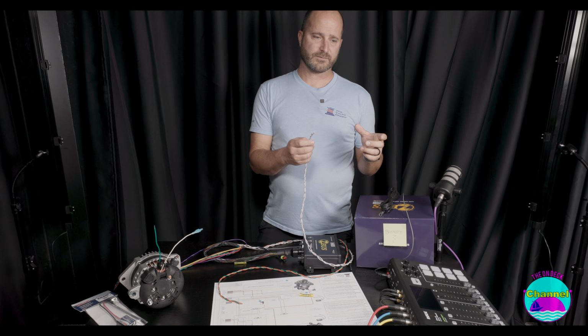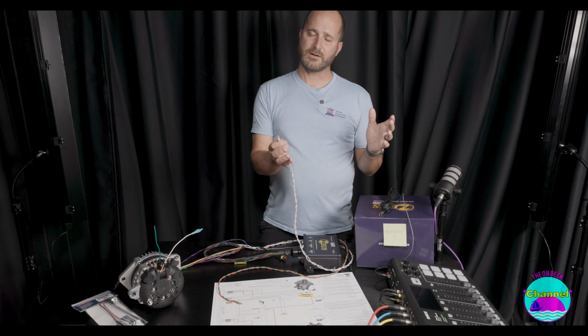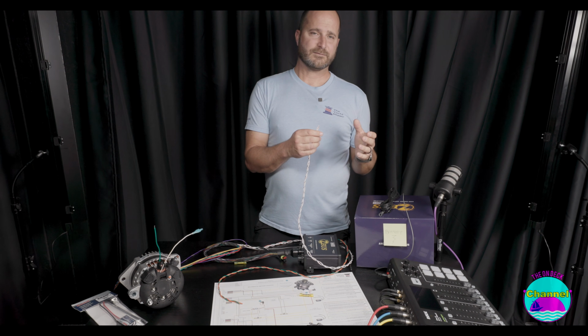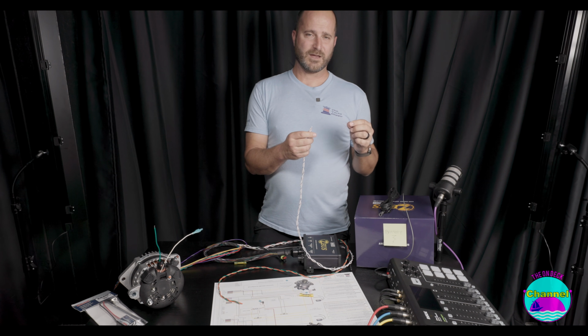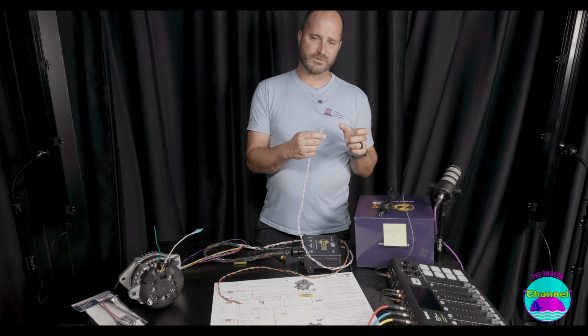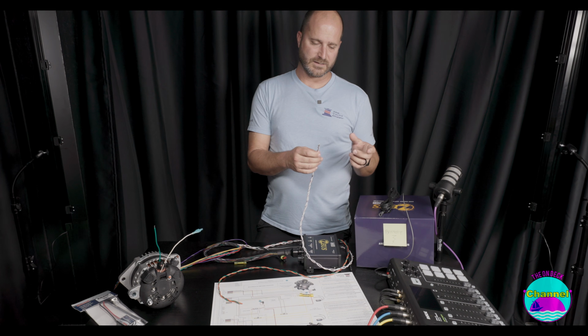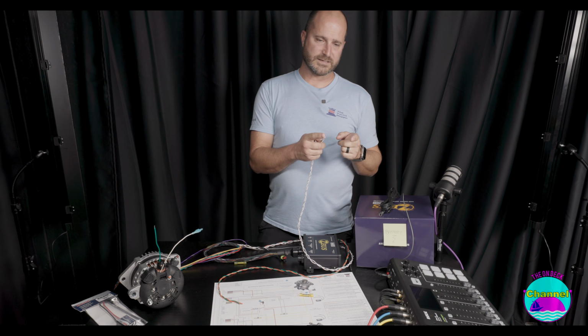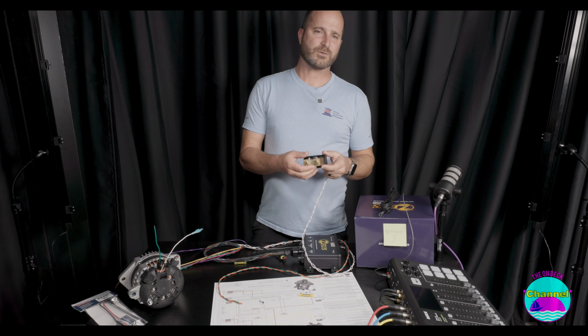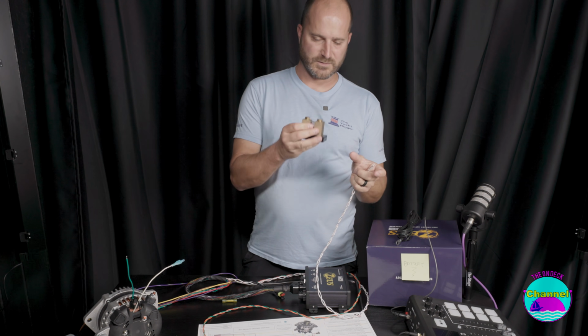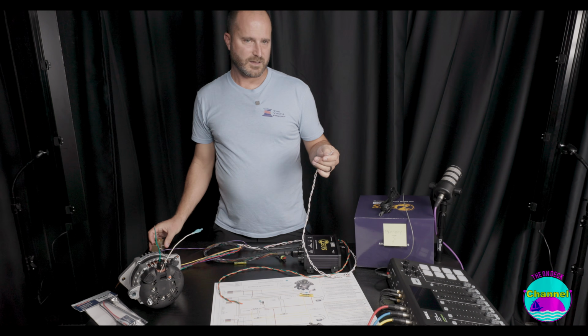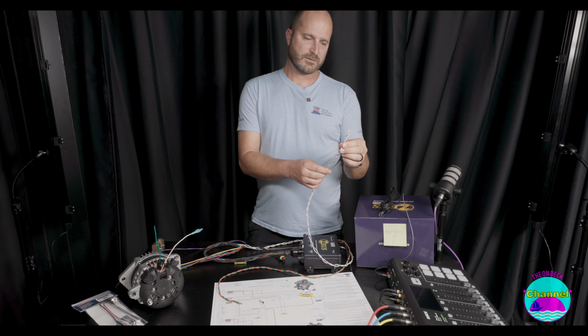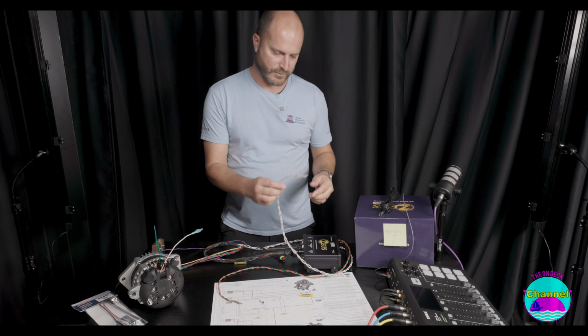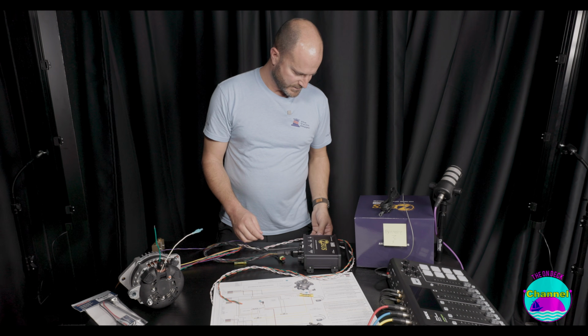With Victron, I've drilled and tapped brass screws on the back side of the shunt. To be transparent, this probably voids the shunt's warranty and may lose a little accuracy since it removes material from the shunt, but I've done it in the past on the Lynx 500—there are analog leads within that, and I could make another video about grabbing analog current from there. It's basically to avoid having two shunts in the system, like a Victron shunt plus this shunt, when it's not necessary. We can cover that in another video. These are the shunt wires for the battery, and they'd be led to the front where your shunt is.